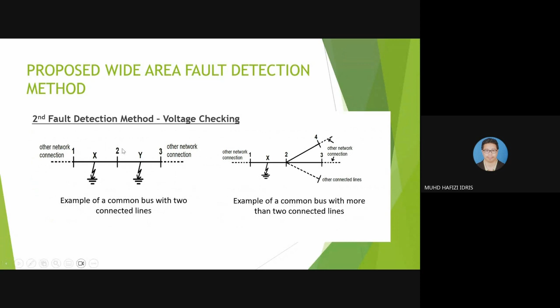For the proposed wide area fault location method, it was developed based on the two terminal impedance method, and it was enhanced by using the Kirchhoff current law and Kirchhoff voltage law to obtain the current and voltage for the terminal which is not connected to any PMU. This method uses negative sequence values as the input.